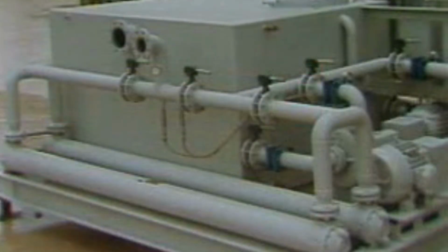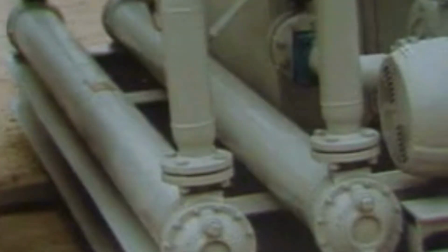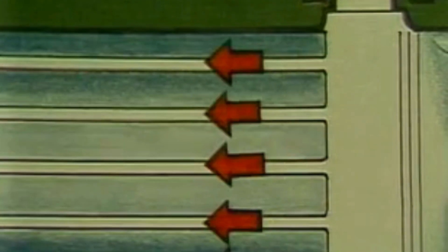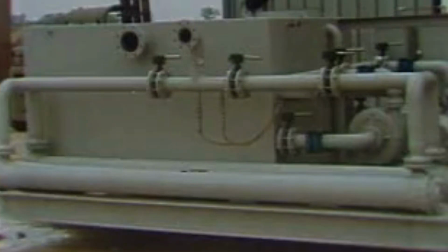Most heat exchanger systems are subjected to an oversupply of cooling fluids to the core. In fact, it's common on most of our rigs to have pumping capacity several times greater than the required optimum volume and flow rate. This can create problems, forcing too high of a volume through the core and/or shell with an increased high velocity of fluids, which will erode the core. It doesn't take long for this state of erosion to cause leaks, and then a replacement of these expensive cores or a complete heat exchanger is necessary.